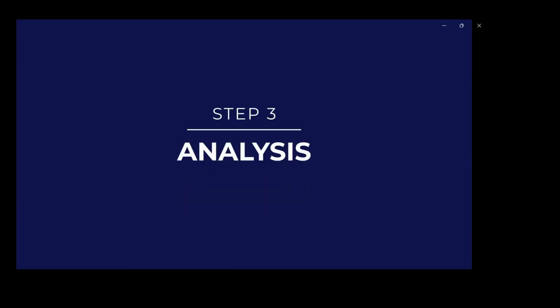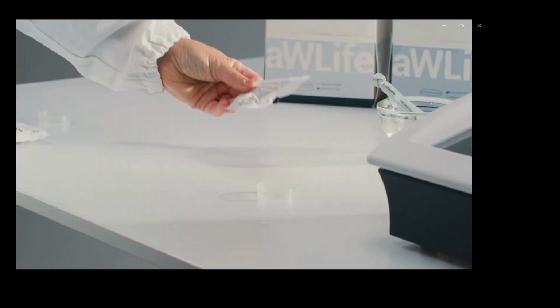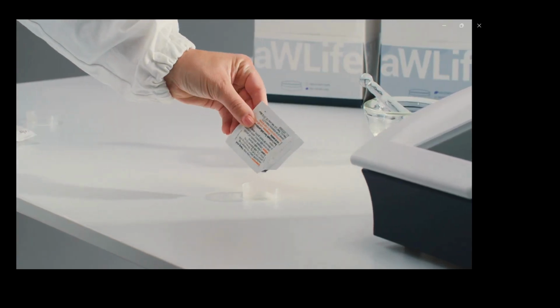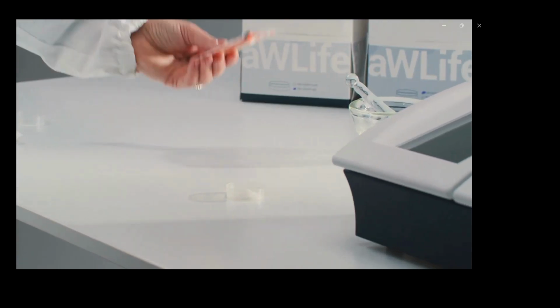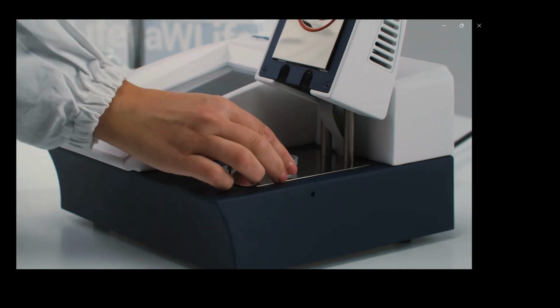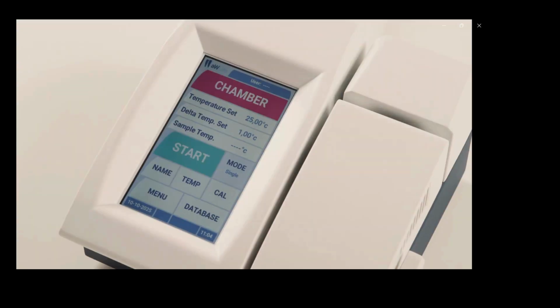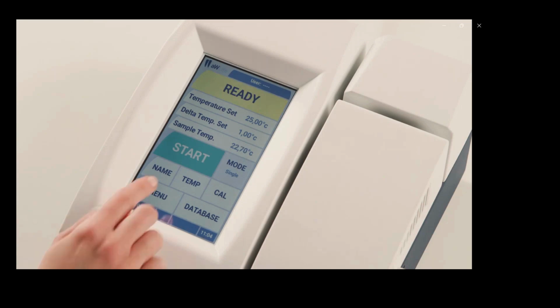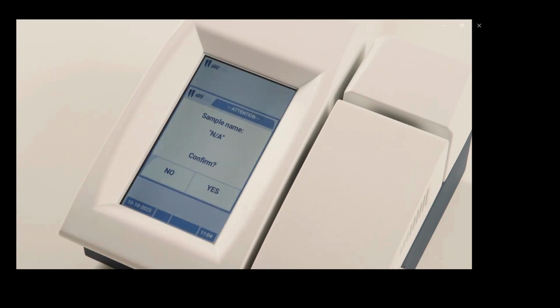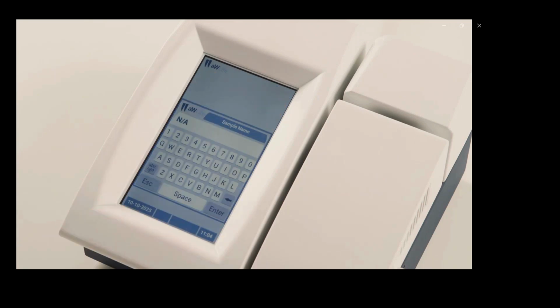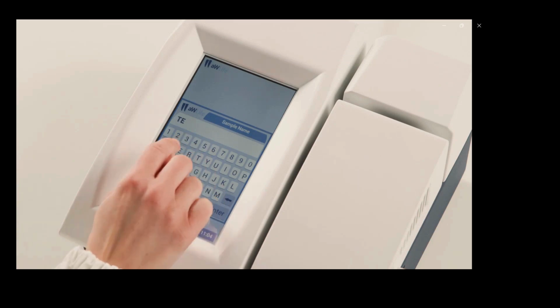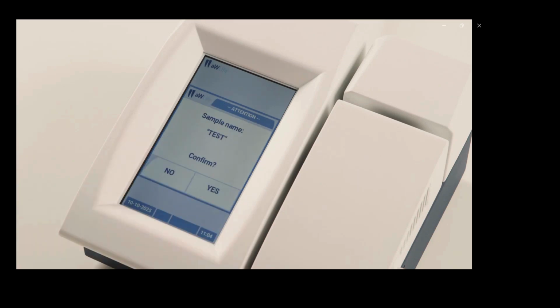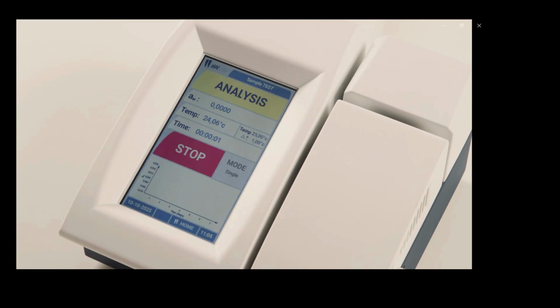Step 3. Analysis. Now we can prepare the samples. Distribute the product evenly inside the sample holder, then place it in the analysis cell. When the instrument is ready, press the Start button to begin the analysis. You will then be asked to give a name to the sample, and then the instrument will automatically bring the sample to the correct temperature. When this is reached, the analysis phase begins.